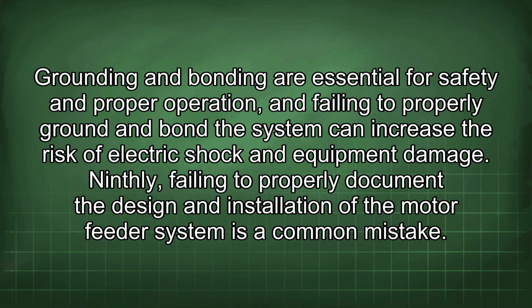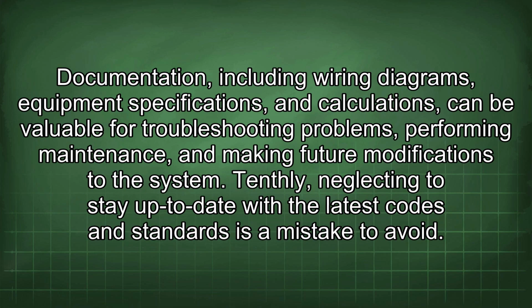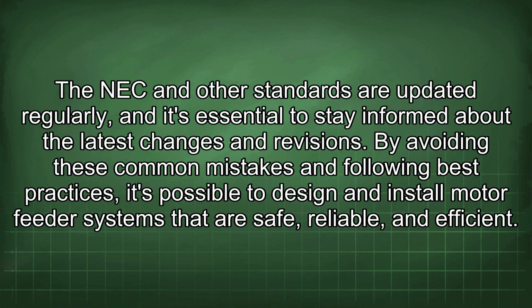Ninthly, failing to properly document the design and installation of the motor feeder system is a common mistake. Documentation, including wiring diagrams, equipment specifications, and calculations, can be valuable for troubleshooting problems, performing maintenance, and making future modifications to the system. Tenthly, neglecting to stay up to date with the latest codes and standards is a mistake to avoid. The NEC and other standards are updated regularly, and it's essential to stay informed about the latest changes and revisions. By avoiding these common mistakes and following best practices, it's possible to design and install motor feeder systems that are safe, reliable, and efficient.